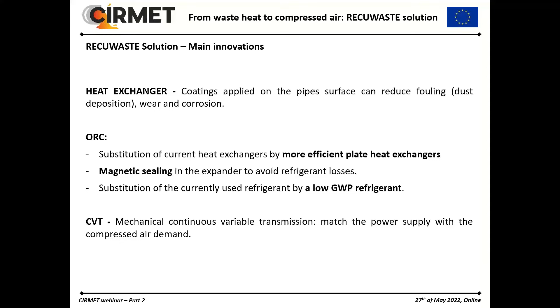Other innovations implemented are the substitution of current heat exchangers in the ORC unit by more efficient plate heat exchangers, the implementation of magnetic sealing in the expander to avoid refrigerant losses, and the substitution of the currently used refrigerant by a less pollutant refrigerant.